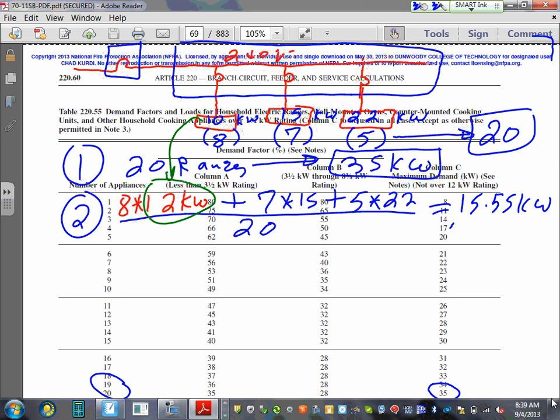From the get-go, if the average is a fraction and 0.5 or larger, it goes up. So this becomes 16 kW. Had this been 15.4, it becomes 15. Even 15.49 becomes 15. Now I'm exaggerating. Anything less than 0.5 goes down, and 0.5 or more goes up. Can you see? Okay, that's step 2.